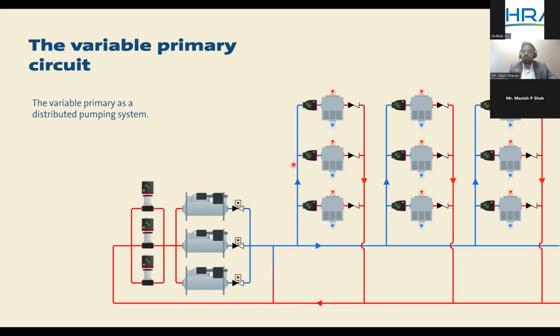Similarly, the head of this pump is going to be calculated the same way, taking the friction from the decoupler and the particular coil drop and the accessories losses and the return line losses till the decoupler. So each unit has its own pump, own driver, where it is driving the water based on the need of that particular unit. That's why we call this decentralizing the pump, or a coil pump, which is having dedicated pumps for each coil. Right now we have multiple ways of doing it. This clearly shows one pump connected to one unit, but we can have a hybrid approach, which I will show in coming slides. But by doing this, the operation philosophy gets very simple, which I will show in a couple of slides, how we operate or modulate the flow and how we balance the flow between primary and secondary.